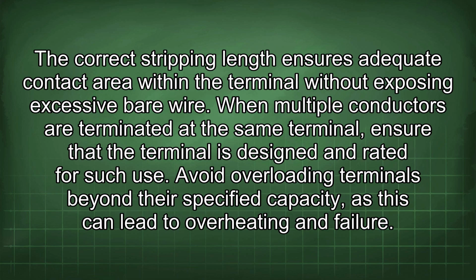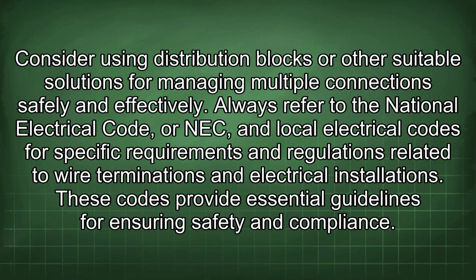When multiple conductors are terminated at the same terminal, ensure that the terminal is designed and rated for such use. Avoid overloading terminals beyond a specified capacity, as this can lead to overheating and failure. Consider using distribution blocks or other suitable solutions for managing multiple connections safely and effectively.